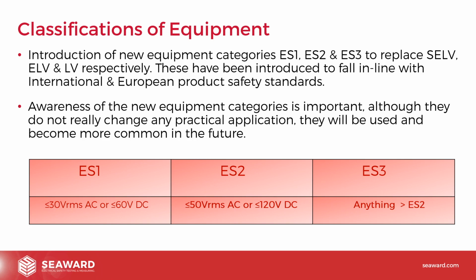So again in here, and we'll probably do another webinar further down the line to go into these things in a bit more detail. There is quite a lot in the appendices of the new code of practice that covers ES1, ES2, ES3. So ES1 generally is equipment less than or equal to 30 volts AC or less than or equal to 60 volts DC. So this is your really safe stuff. This is the stuff you might be using in bathrooms and sensitive locations.